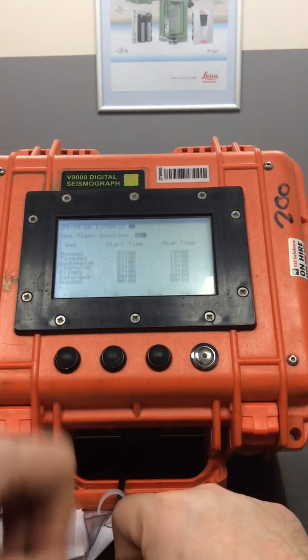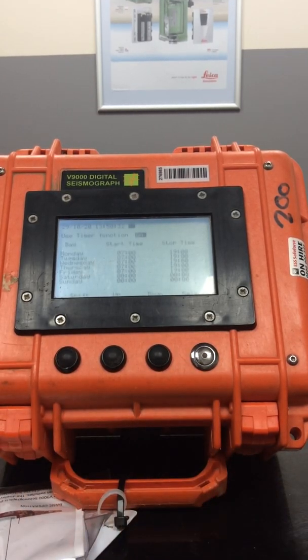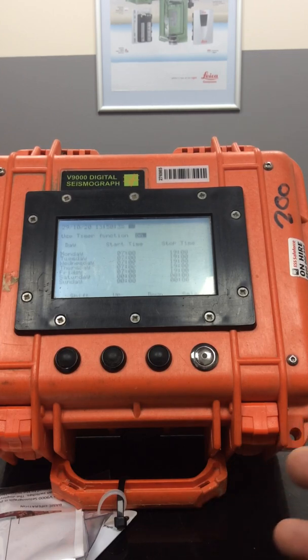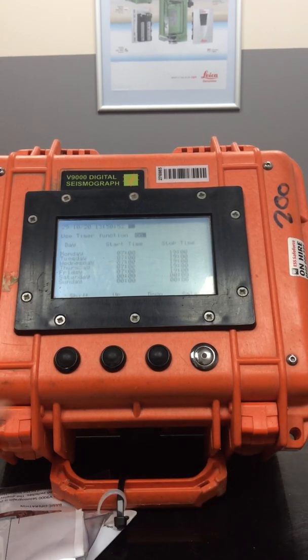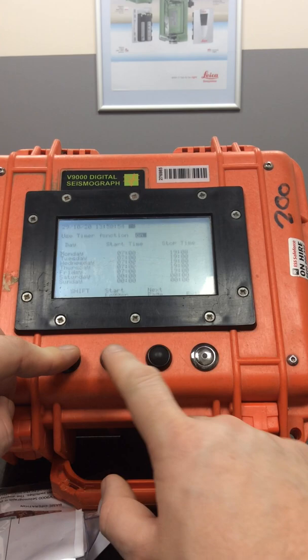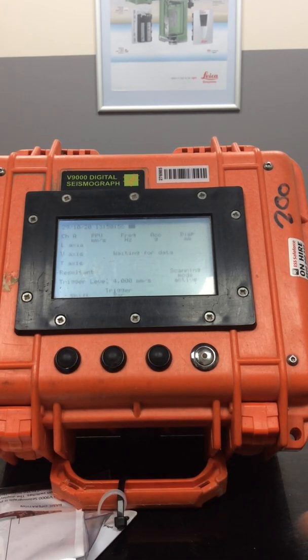Shift again, next page, and you've got a timer function here that you can set up if you wanted to. Say for example you turn the unit on at 8 o'clock in the morning, but you've got a piling machine turning up at 11 o'clock till 2 o'clock and you just want to monitor it during those times, you can set those times as per that. Then once you've done all of those settings, to start the unit recording, you would hit Shift, Start Logger. That saves the settings you've done and then starts recording the data.